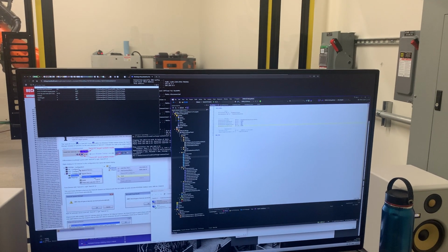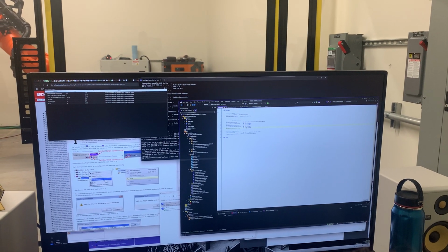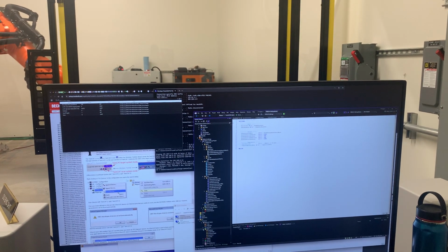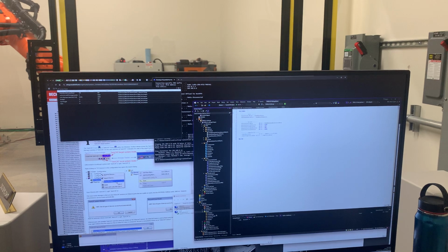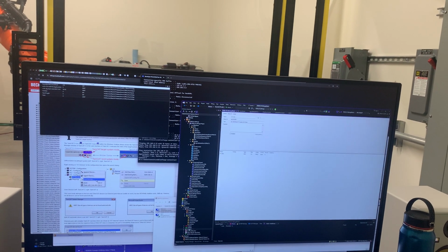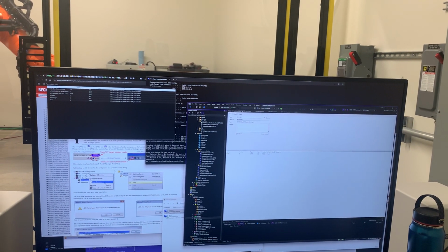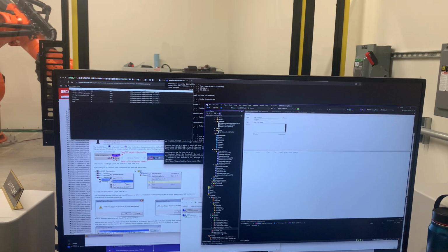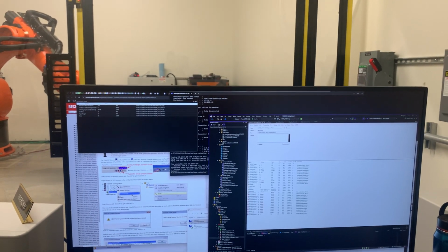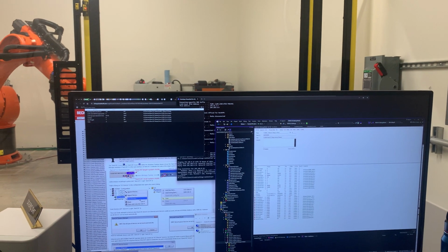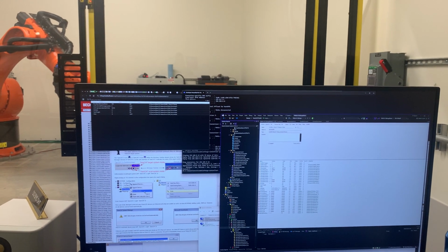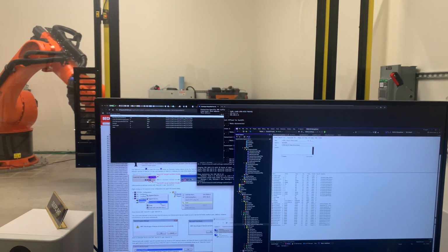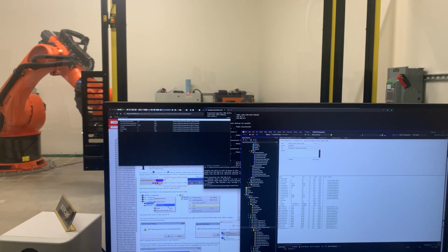Once you build the program there, you can come down to the EtherCAT devices under EtherCAT master, and you can see everything there. The EK1100 is the I/O block. On the end of that is the bridge, the EL6695 bridge, one up from where you're at. If you drop that down and go to inputs, that's all the data transfer to and from the robot, the input and output.